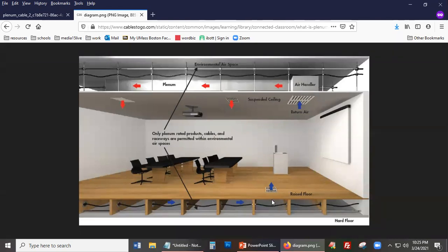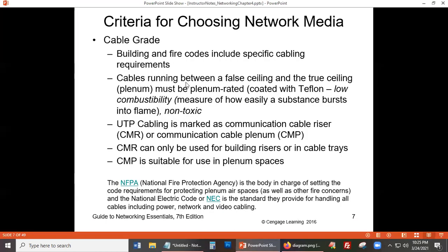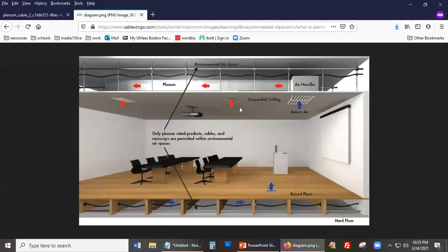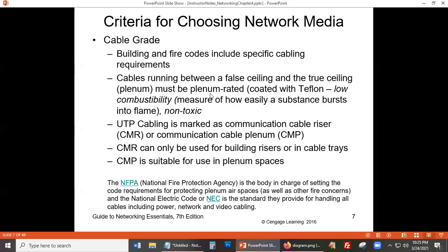It's very important that the kind of cabling used in plenum spaces follows the specifications for plenum spaces. Cables running between the false ceiling and the true ceiling in the plenum space must be plenum-rated. Plenum-rated cables must be specifically designed for plenum spaces. Plenum-rated cables are coated with Teflon.